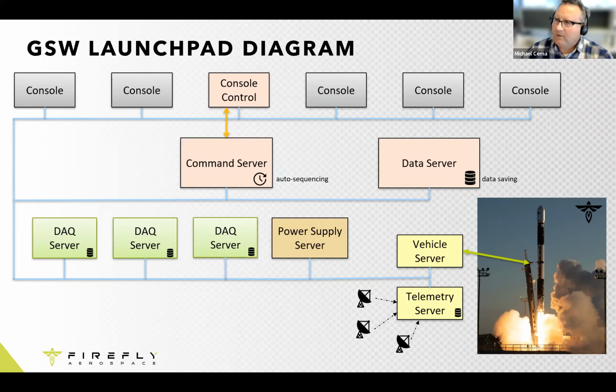I'm not sure I understand exactly the question, but for any kind of tight control loop, for instance a local PID or control loop, we would run that custom on the DAQ server itself. So it would have access to its sensor data immediately. That's within 10 milliseconds or less, and then it would do local control there.